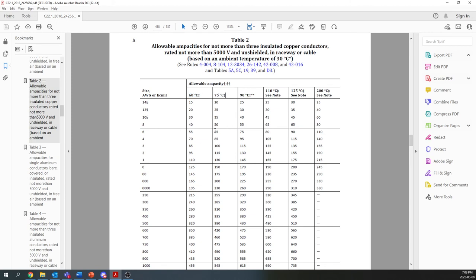So for the 75 amp load, we have to go to the next highest one here, which is between 65 and 85. So we're picking a number 4 AWG wire, for American wire gauge, which is the common gauge. So 4 gauge wire, number 4 wire. And for the 50 amp load, we can use a number 8 wire. So that's great, now we have our two wires. At the end of the day, we're going to have 2 number 8 wires and 3 number 4 wires. So 5 wires, 2 different sizes.